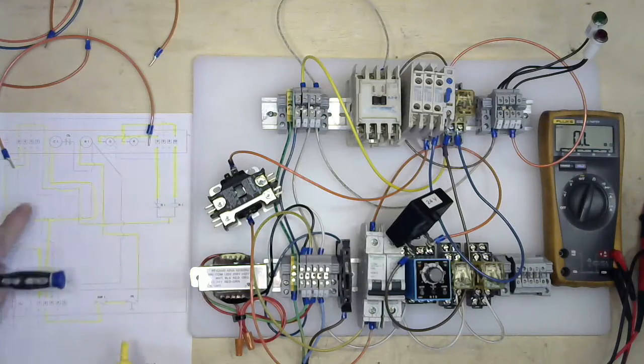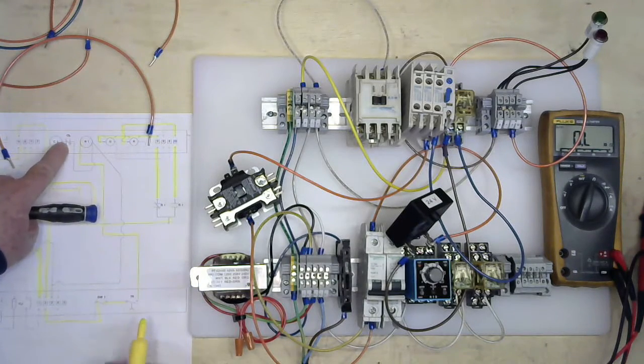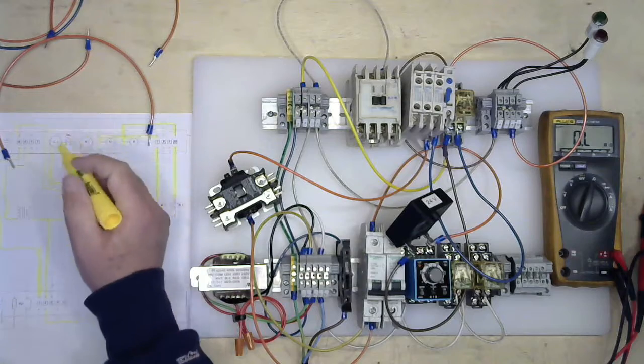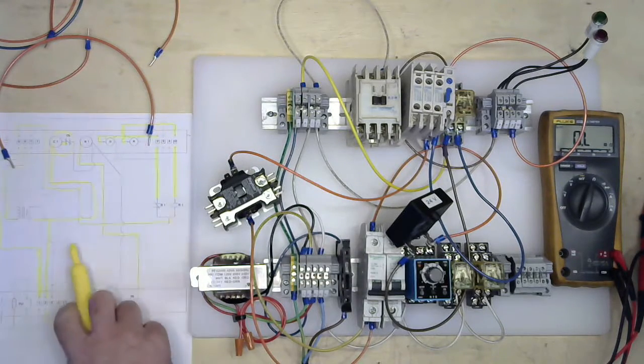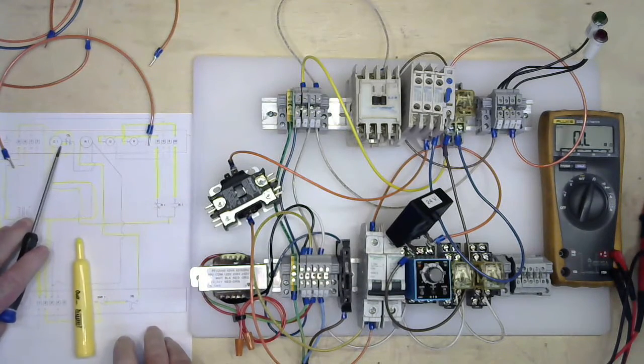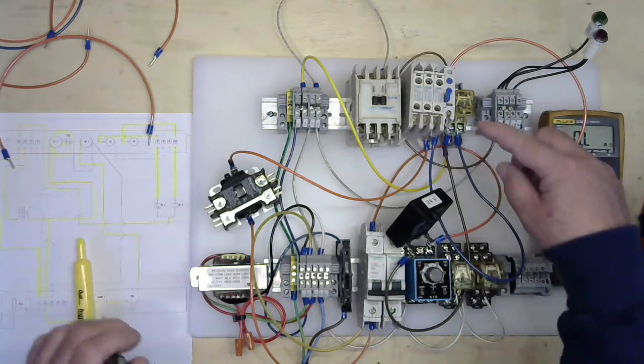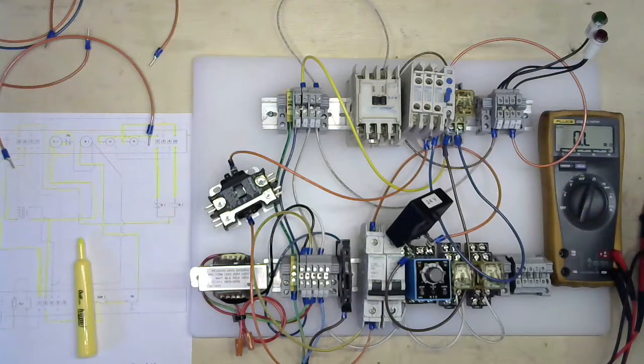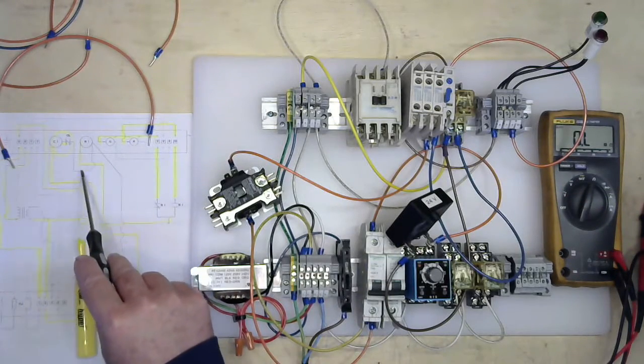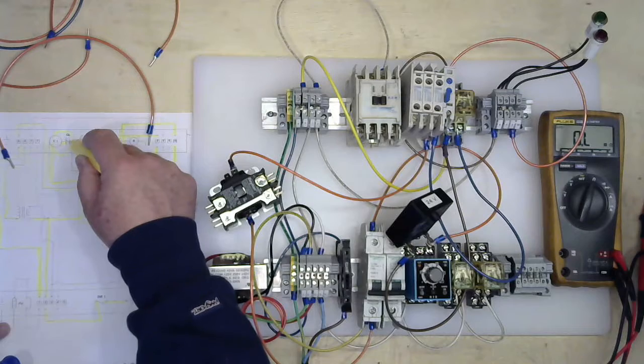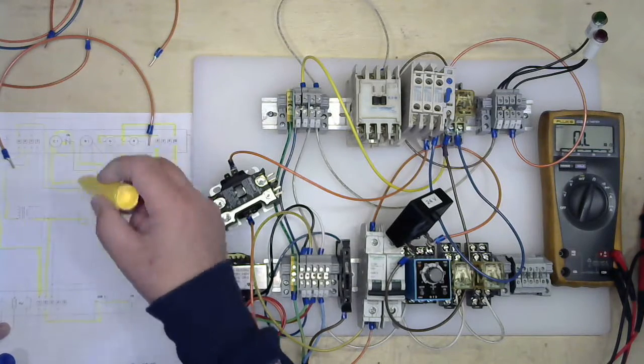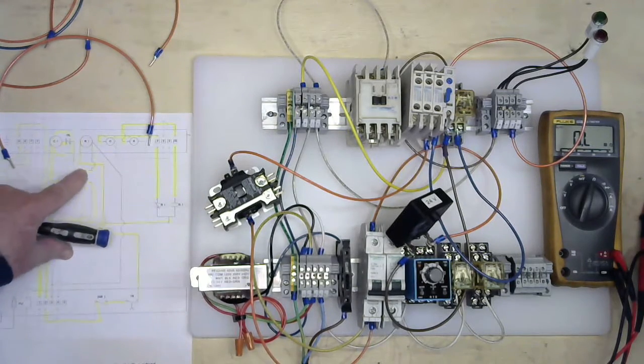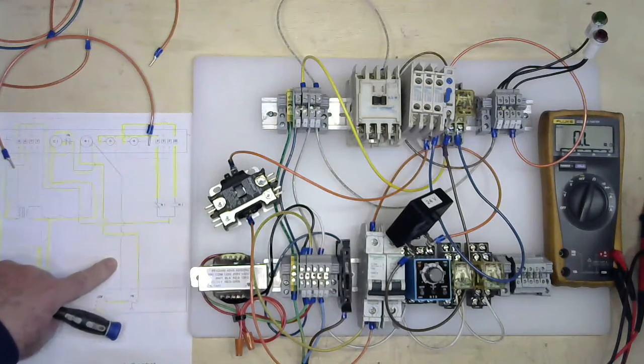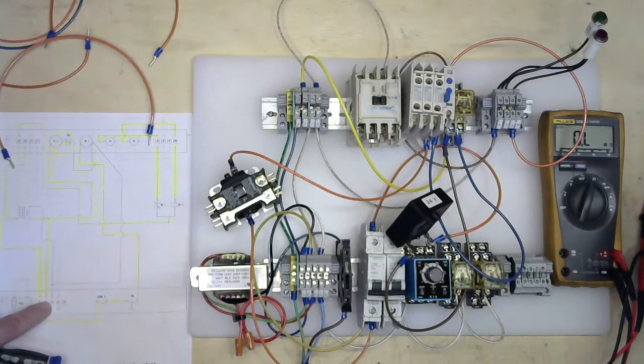So if you look at your schematic, this very little set of wires right here is the only connection point we just made. It looks small on the schematic, a little bit bigger out here in the field. Now, we made this connection from here back to the relay. So we went to 95, 96 to our relay, and now, at the relay, we have to make a wire coming back to terminal number 3.